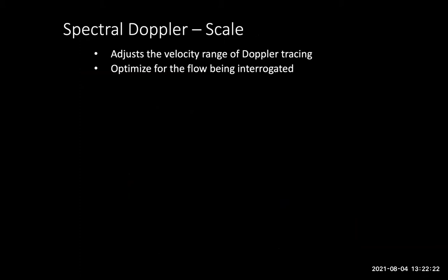Like in color Doppler, the scale adjusts the velocity range we want to display, and we will optimize it for the flow we are interrogating. Here the scale is too small, which results in aliasing, or when the velocity exceeds the scale and wraps around. So we can increase the range to allow us to see the whole flow pattern so we can measure it correctly.